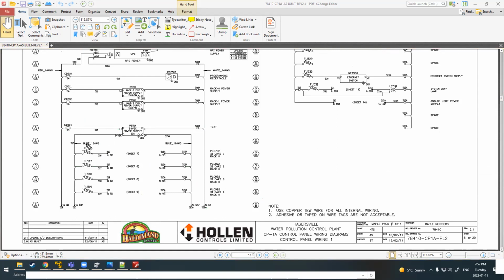With the 24-volt power supply, you can see here in this drawing they don't have the details. I'm assuming this means that they don't have enough room to put all the details for that. So it says sheet 7. Yes, perfect. So here you'll see this branch in here is separate from 120. This is 24 volts DC. So when you're looking at these, especially if you have a meter and you're troubleshooting a panel, it's good to follow that. And you know this is 24 volts.